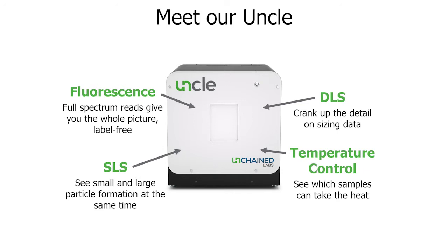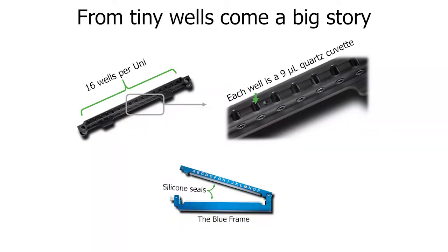All measurements are done with temperature control, so you can make measurements at room temperature, elevated temperature, or more commonly across a thermal ramp. The UNCLE's key feature is the Uni sample holder — an array of 16 quartz cuvettes easily loaded with a pipette. The high-grade quartz provides great optical sensitivity for fluorescence and light scattering data, and the anodized aluminum frame provides efficient heat transfer. After loading, the sample is clipped into a blue frame where silicone gaskets ensure the sample is always sealed with no risk of evaporation as temperature increases. The Uni provides a combination of throughput and small sample volume.